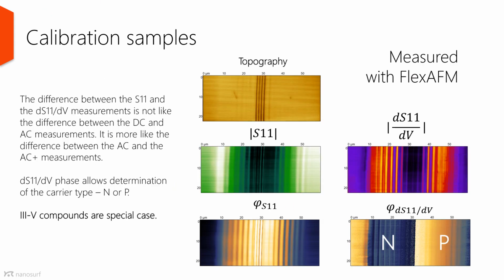In the S11 measurement, it is not possible to judge what type of the dopant is on which side of the sample. In the dS11/dV, same as in the dC/dV measurement, the phase information can indicate the type of the carriers, as can clearly be seen on the image in the right bottom corner. This phase difference is coming from the difference in the mobility between the electrons and holes.